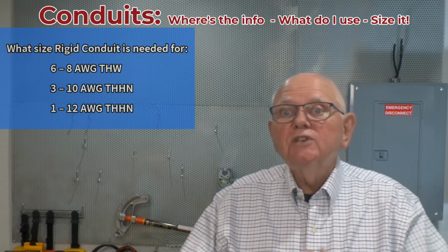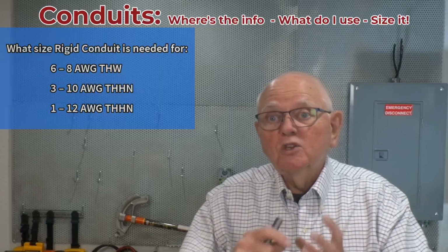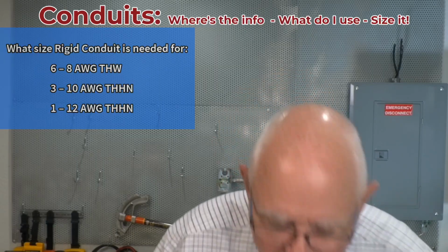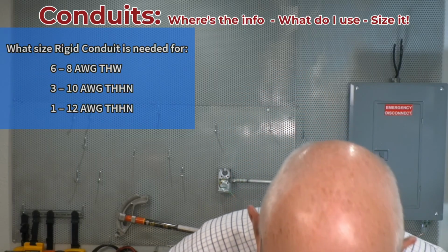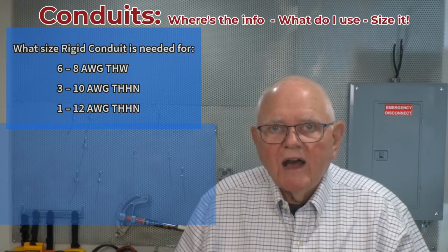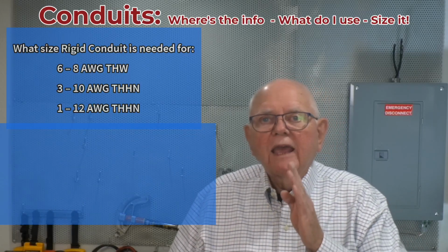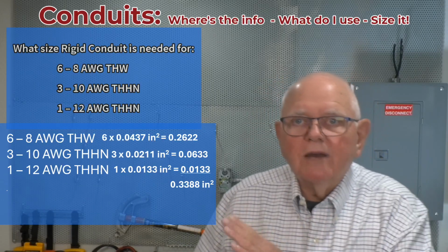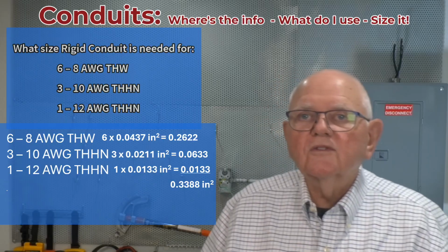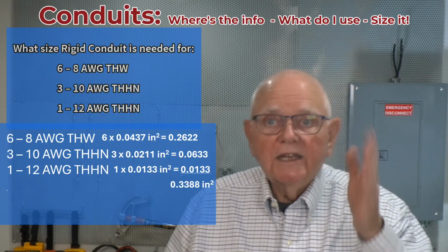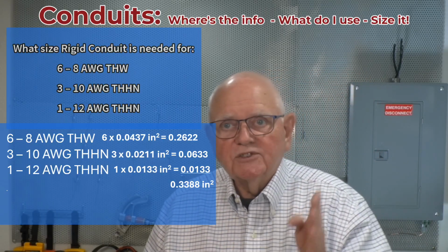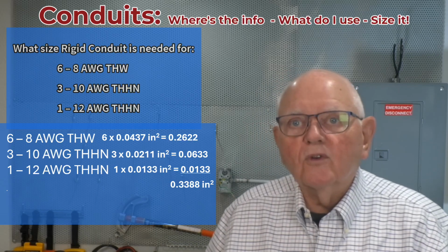Well, I need to know what's the area in square inches of all these different conductors. So I look at table 5 and I find out that number 8 THW is 0.0437 square inches. I have 6 of them, 6 times that 0.0437.